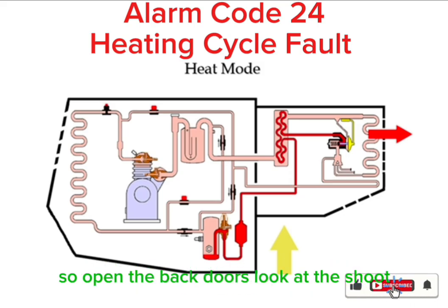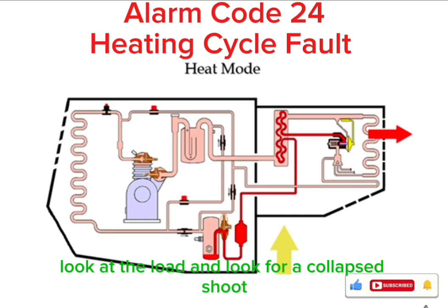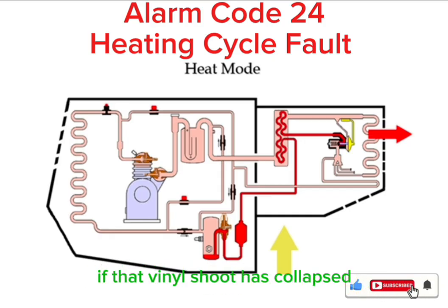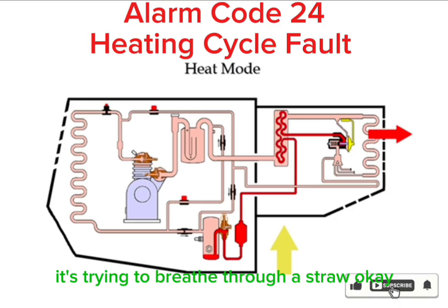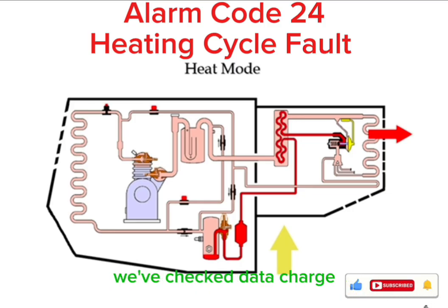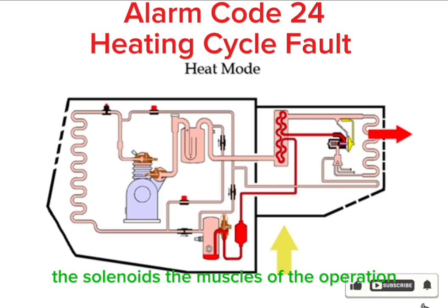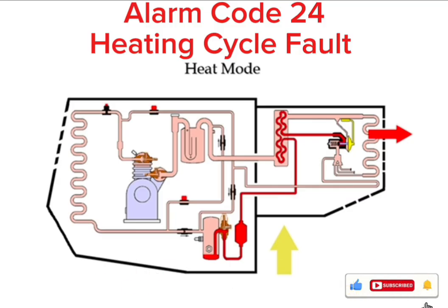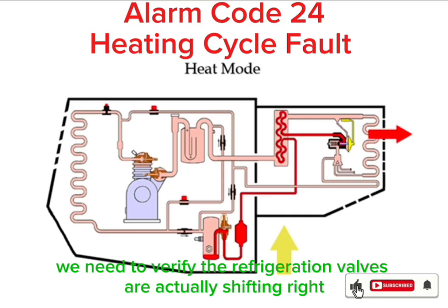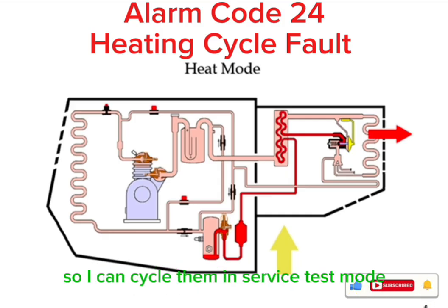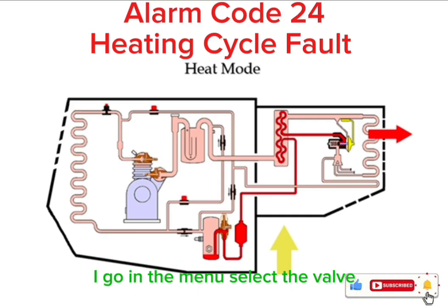So open the back doors, look at the chute, look at the load. And look for a collapsed chute. If that vinyl chute has collapsed, you're suffocating the unit. It's trying to breathe through a straw. Okay, we've checked data, charge, pressure, sensors, and airflow. The unit still fails. That leaves us with the hardware. Step 6, the valves. The solenoids, the muscles of the operation. We need to verify the refrigeration valves are actually shifting. Right, so I can cycle them in service test mode. I go in the menu, select the valve, hit on, and listen for the click.